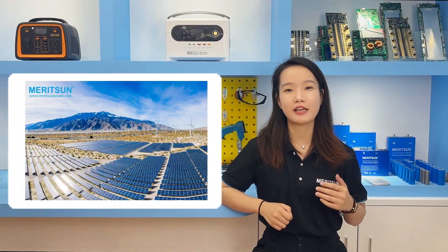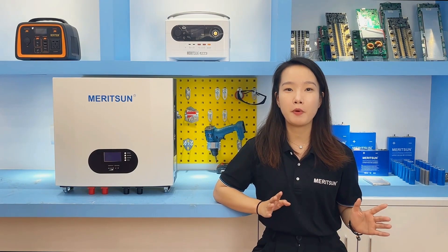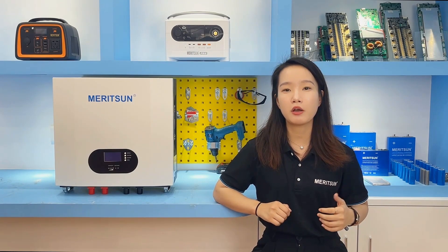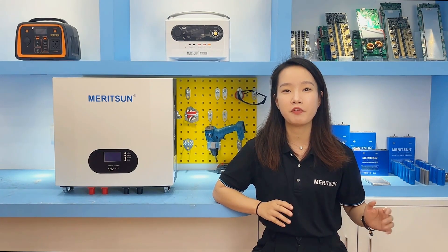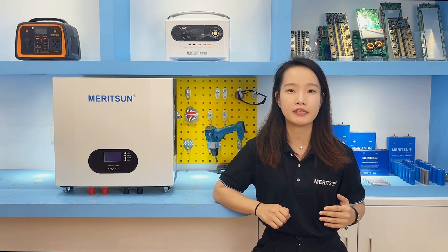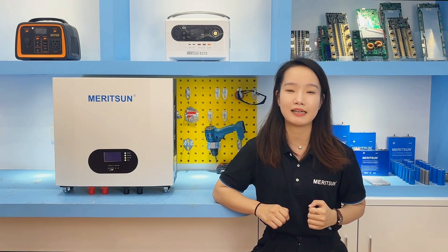For large solar systems such as home energy storage, commercial and industrial solar — in this type of solar system, the components mainly include the solar panel, inverter, and lithium batteries. The composition of the lithium battery pack needs to consider the inverter specifications, such as inverter power, DC voltage range, working current, and the type of power the battery needs to supply in the system. These factors will determine how many kWh of battery is needed and what type of battery product form is selected.